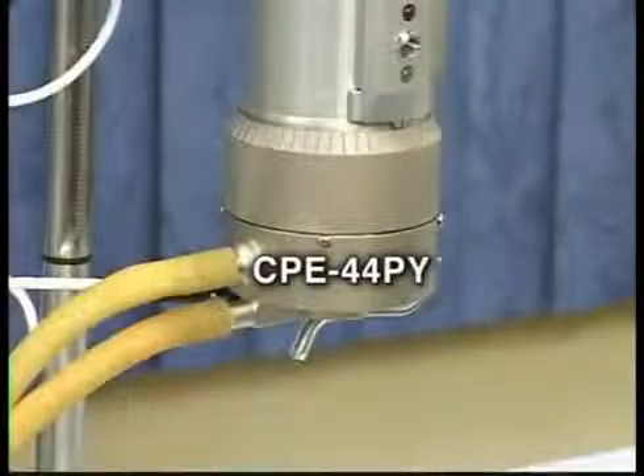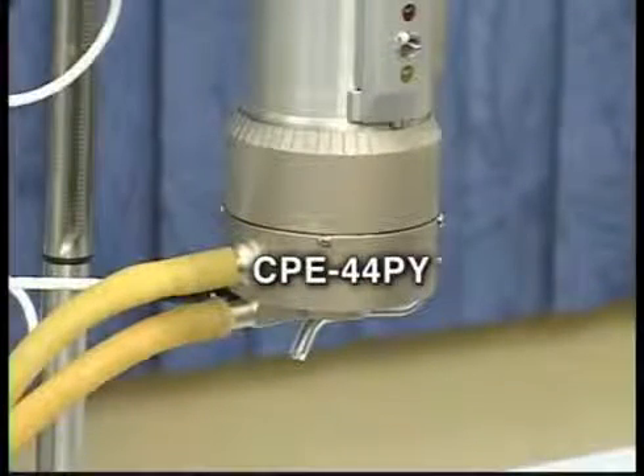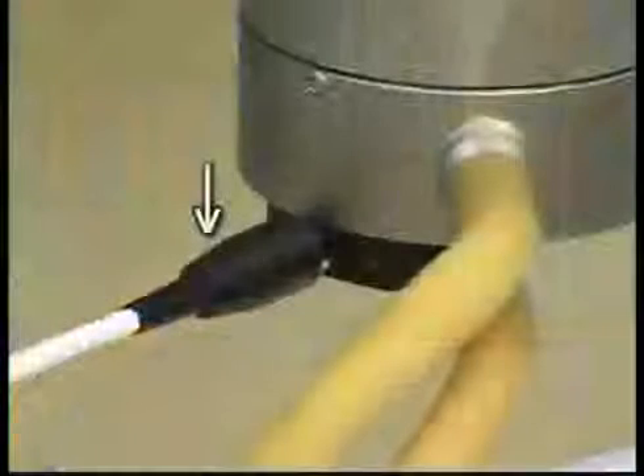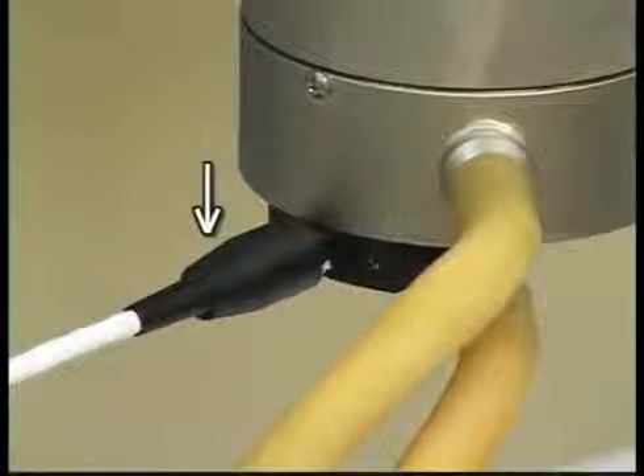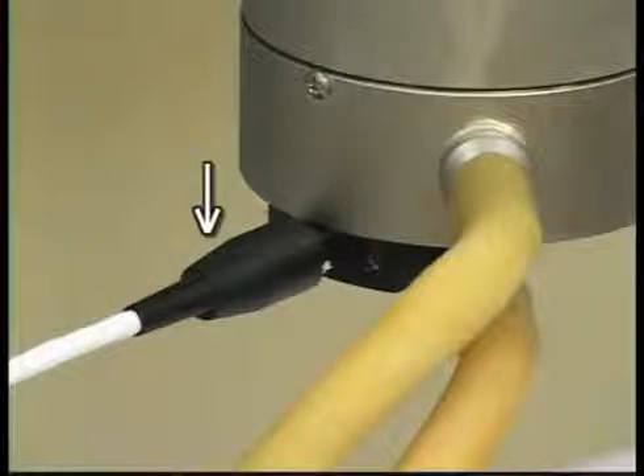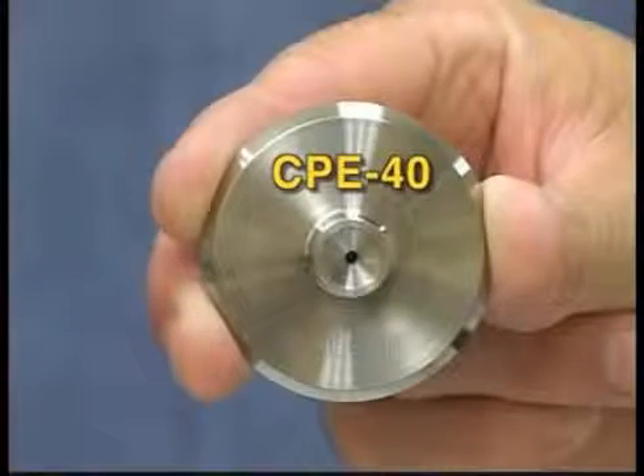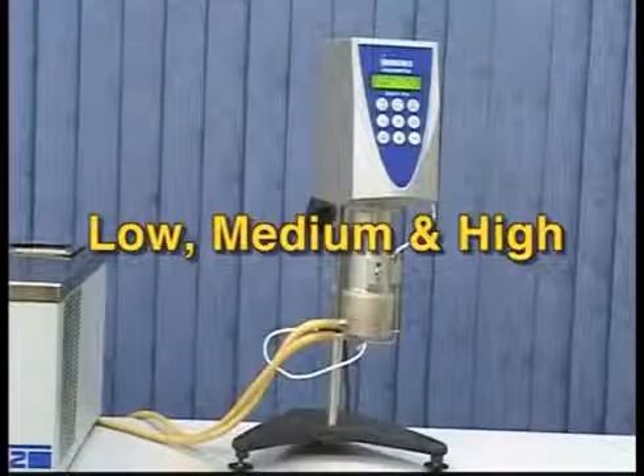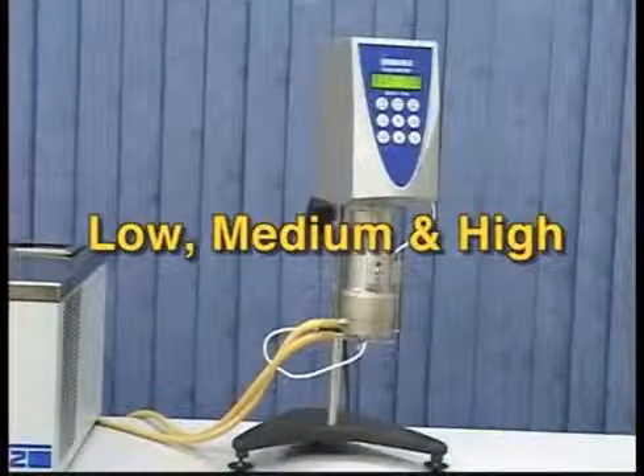The CPE-44PY cup we are using has an embedded temperature probe which allows for temperature monitoring at the instrument. Based on the CPE-40 cone spindle we will be using, select 3 speeds that will give you a low, medium, and high torque value.